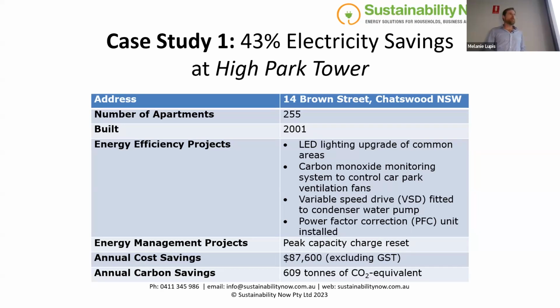They had a condenser water plant as well, which was running 24 hours a day, 7 days a week, pumping water around the building to take heat away from the packaged air conditioning units, like these ones up in the bulkheads here, because there's nowhere convenient in most apartment buildings to put an outdoor air conditioning unit. If you think about a split system air conditioner that's air cooled, you have an indoor part and an outdoor part, so the heat gets taken out of the room and then blown out into the day via a fan. There's a lot of buildings with no space for that outdoor unit, so they basically have a water heat exchanger and run a loop of water around the building that takes that heat up to a cooling tower and then sends it away.